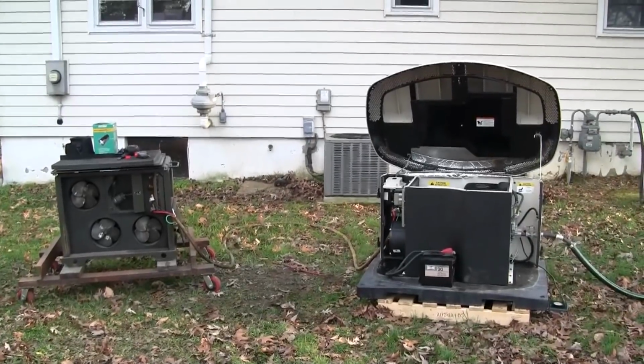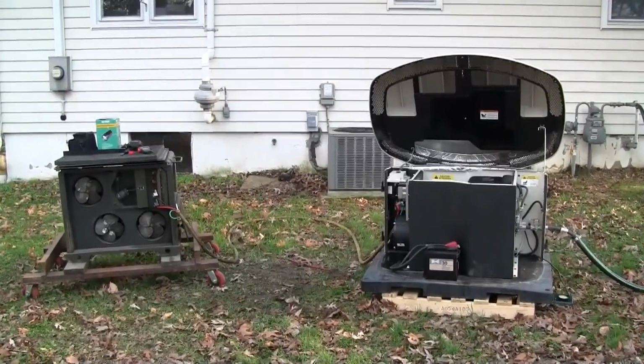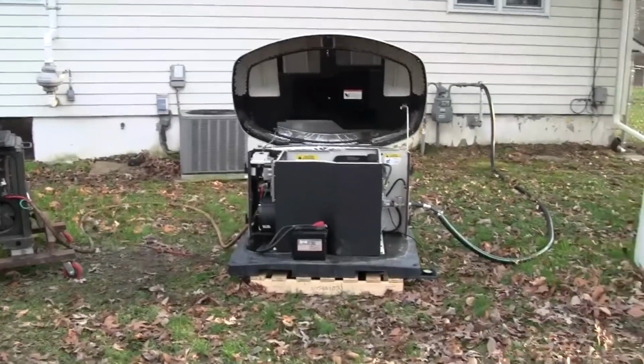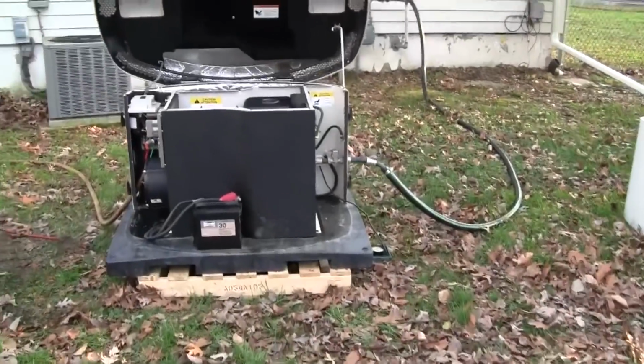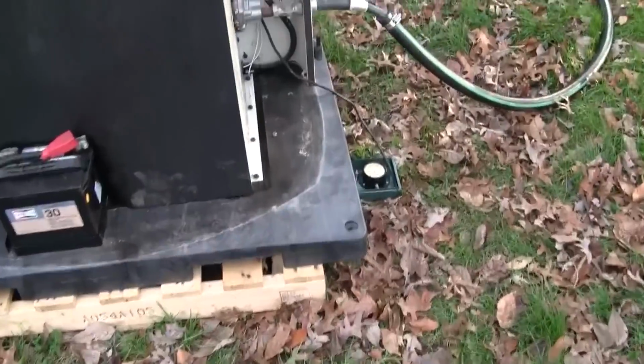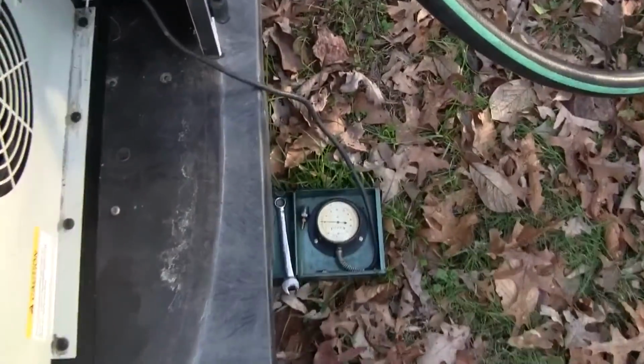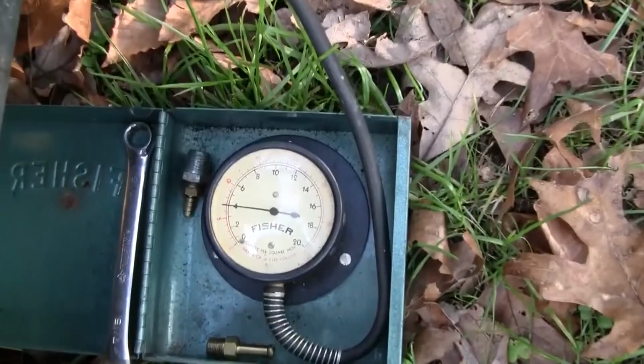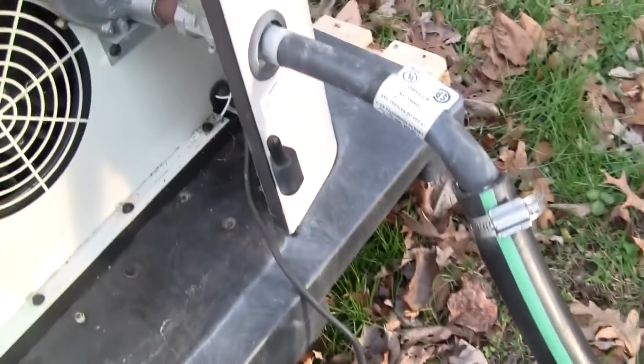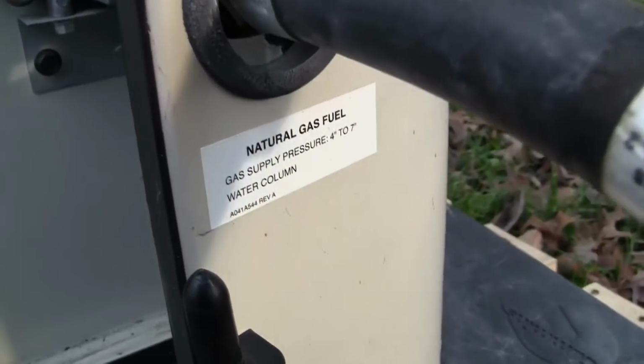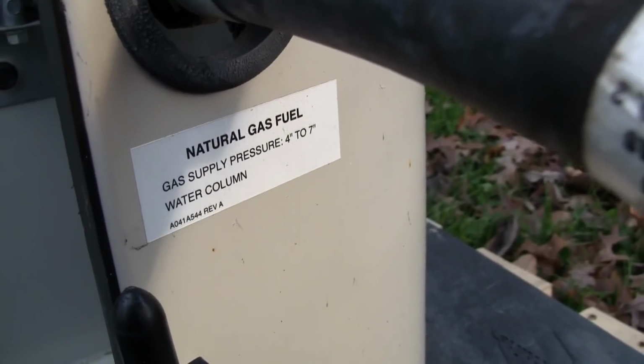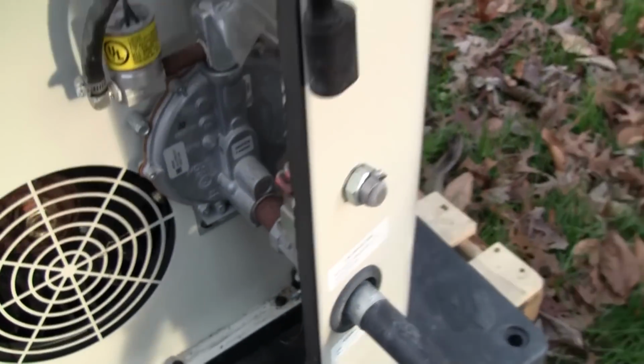Okay, so we are hooked up and all ready to test. Got the generator on the right and the load bank on the left. Generator's hooked up to gas. Got a pressure gauge over here. We've got to monitor the gas pressure feeding the generator. There's a little tag right here. Natural gas, 4 to 7 inches of water column.